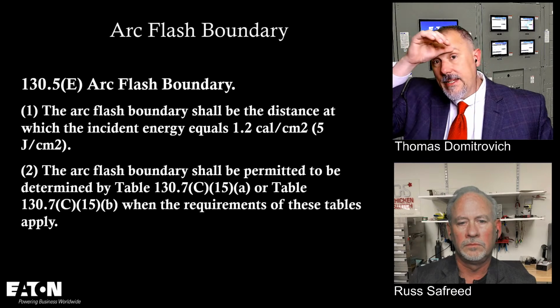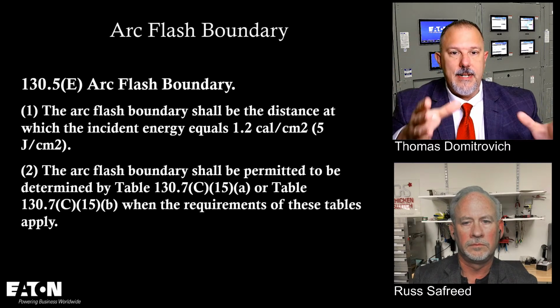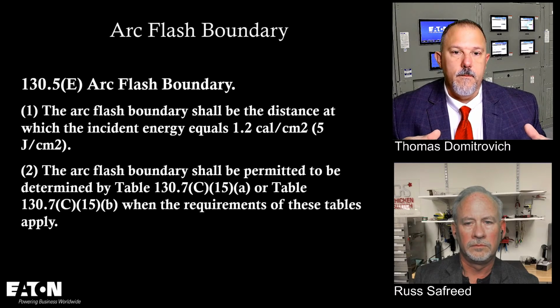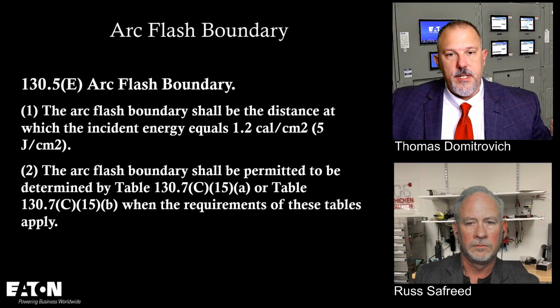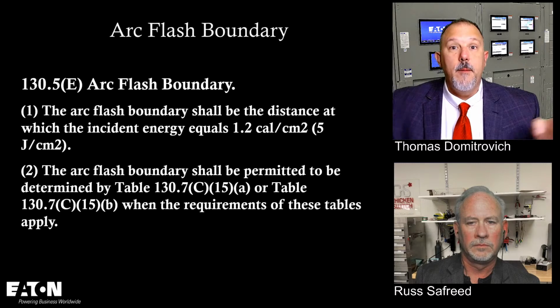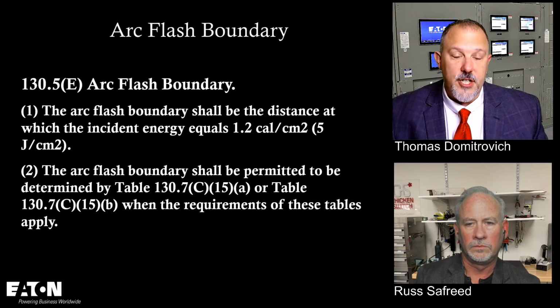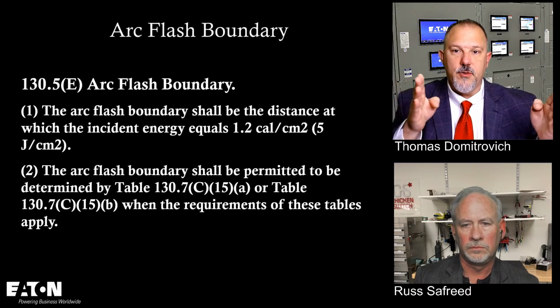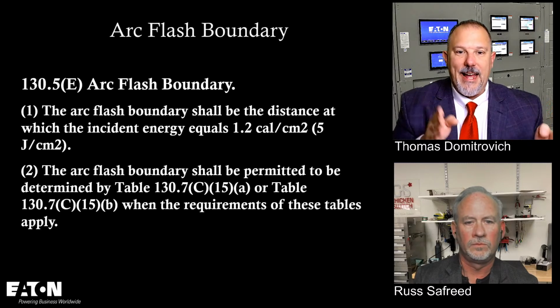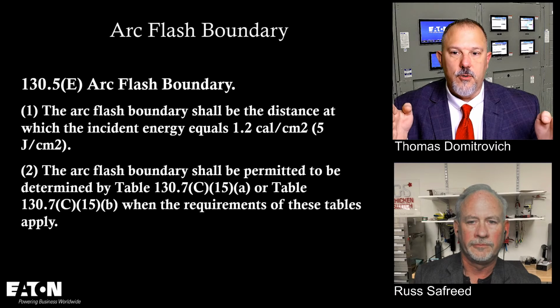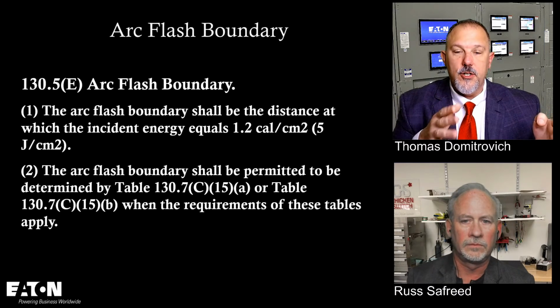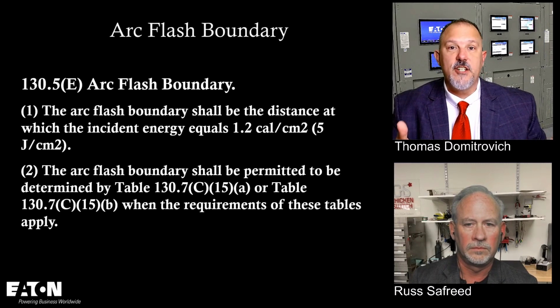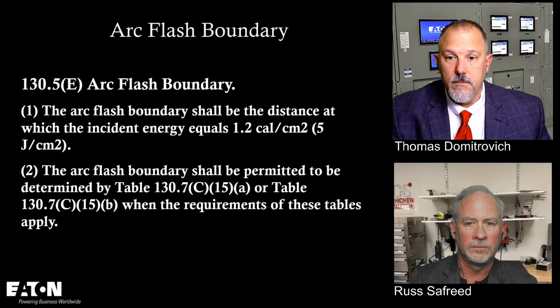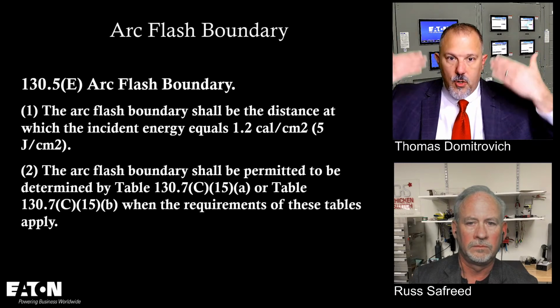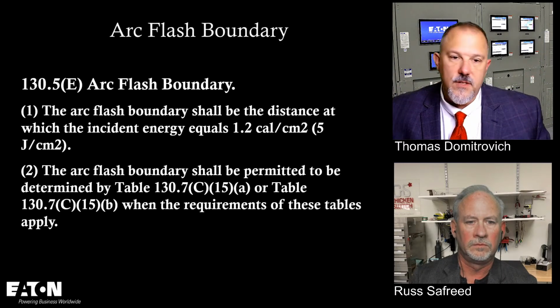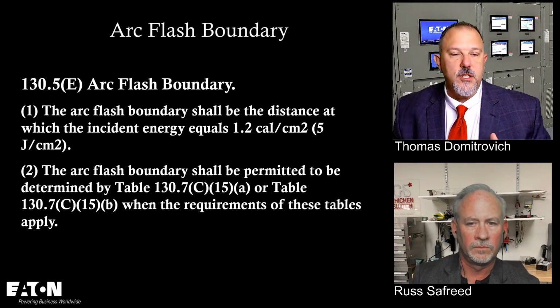So if I look at what my incident energy is at 18 inches, I will keep increasing my arc flash boundary to get to 1.2. But if at 18 inches my incident energy calculation is like 0.5, then my arc flash boundary has to get a little closer, because now at 18 inches I'm at less than 1.2. To get a higher incident energy, I have to get closer and closer to the arc. So there could be some cases where my arc flash boundary is less than 18 inches, and now I'm worried about my gloves as opposed to the whole arc flash. I still have my face shields and things like that I dress for, but my arc flash boundary could be smaller.